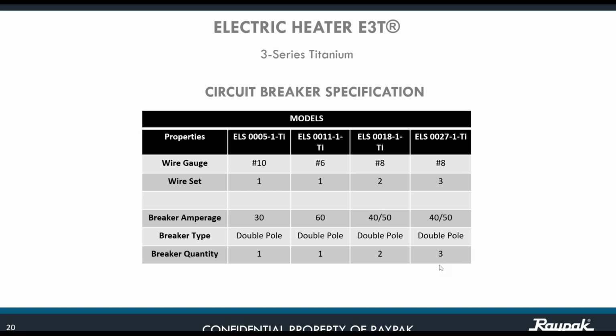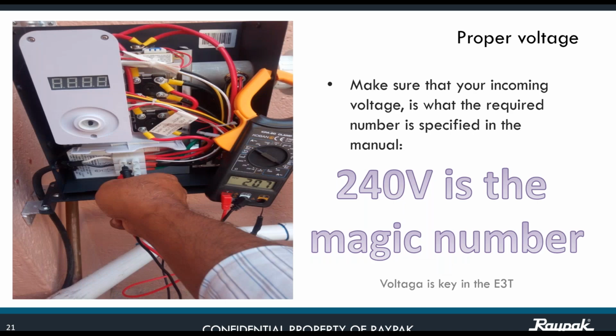Okay, breaker type is going to be a double pole breaker for all of them. Breaker quantity for each of the models is going to be 1 for the 5.5, 1 for the 11, 2 for the 18 kilowatts, and 3 for the 27 kilowatts. Okay, make sure the incoming voltage is what the required number specified in the manual.